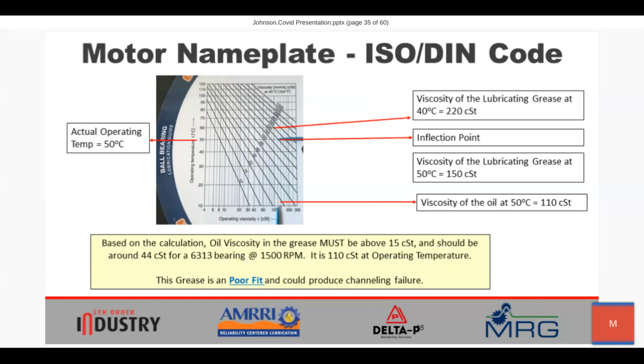Once again, we can use the values on the backside of the calculator to determine whether or not the grease is a proper fit. In this instance, if we were using a general purpose grease made from an ISO 220 viscosity grade, we see the diagonal line for the 220 here. If the bearing is operating at 50 degrees C and we're using an ISO 220, that gives us 110 centistoke. This shows us why general purpose greases are not a good fit for electric motors.